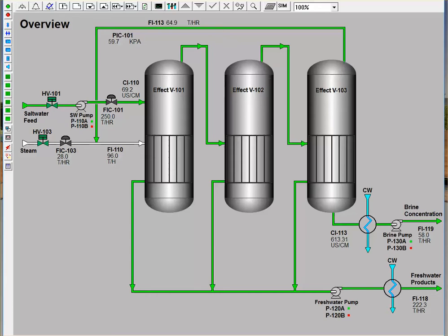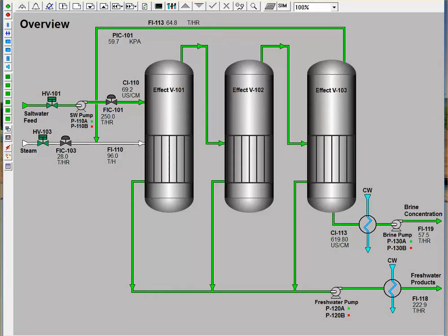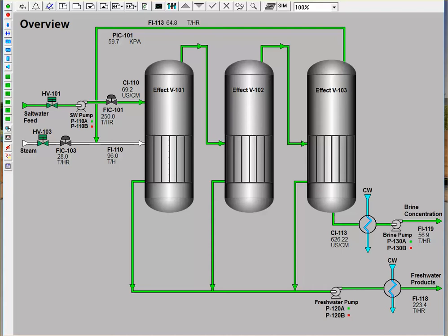Initially, external steam is used to heat the process flow of salt water. This process tries to utilize maximum energy for the separation across multiple vessels, or effects. This particular simulator contains three effects, in which external steam only enters the first vessel but provides enough heat for the entire process. In addition to the steam, the salt water feed enters the first evaporator. The steam condenses and transfers its heat to the salt water mixture, producing outlet streams of pure water vapor and concentrated brine.